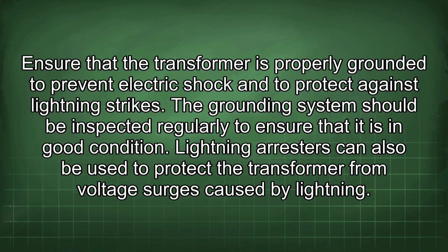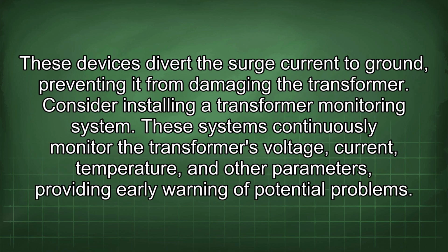Ensure that the transformer is properly grounded to prevent electric shock and to protect against lightning strikes. The grounding system should be inspected regularly to ensure that it is in good condition. Lightning arresters can also be used to protect the transformer from voltage surges caused by lightning. These devices divert the surge current to ground, preventing it from damaging the transformer.